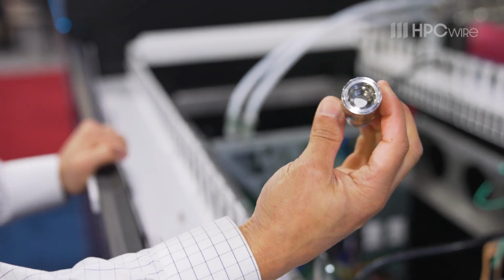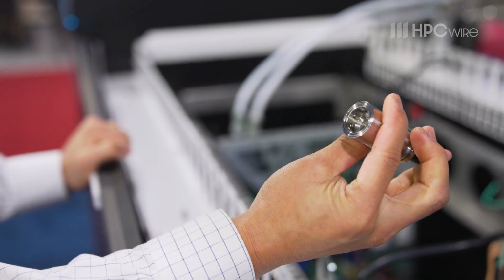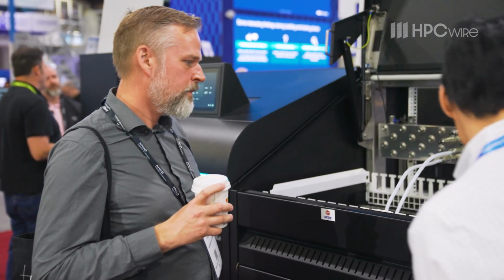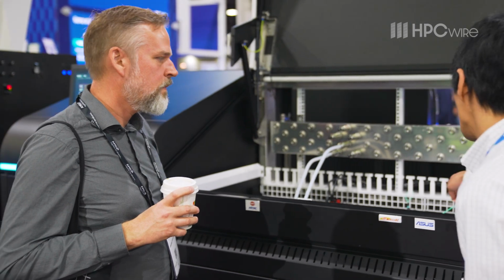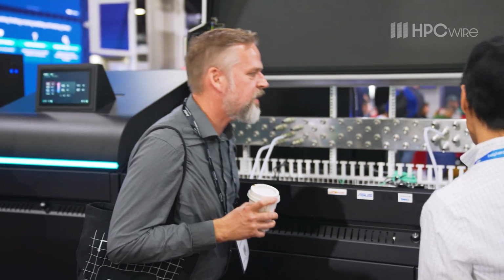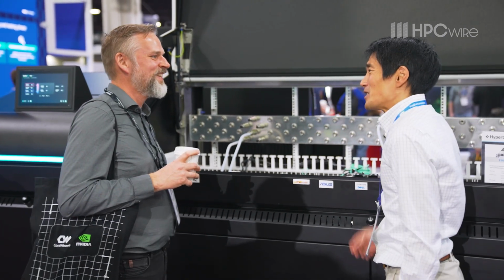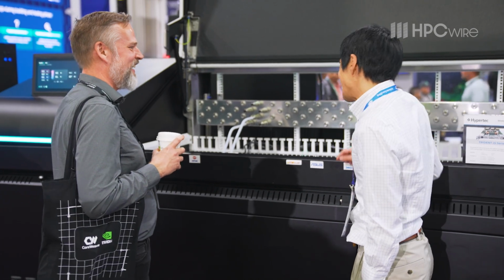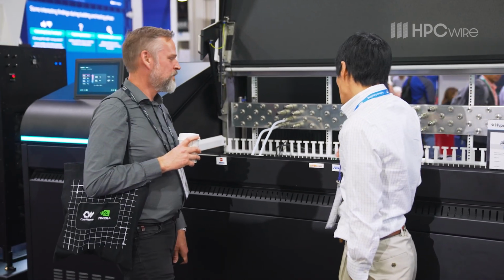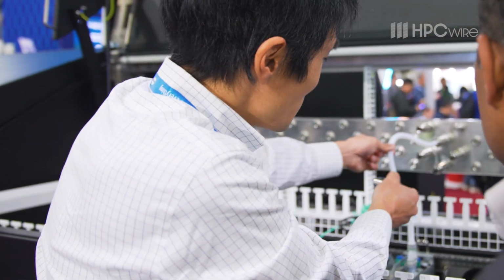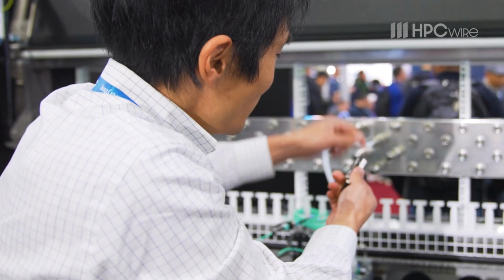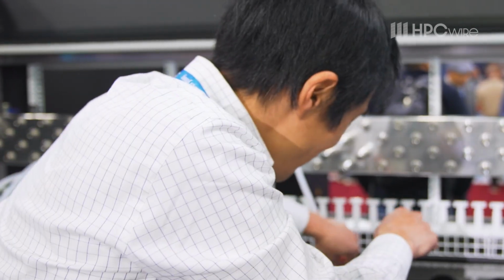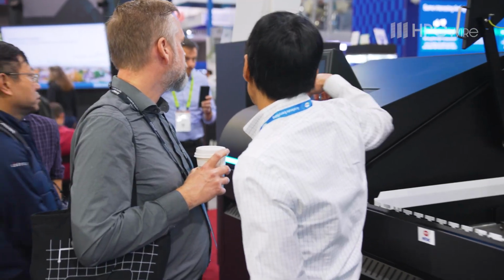Targeted flow technology works similar to DLC. You have a cold plate like heatsink on the CPU or the GPU. The main difference is that with DLC, the cold plate has an inlet and an outlet so the water can come from and to the manifolds. With targeted flow, there's only an inlet, so the fluid gets pumped from the manifold to the inlet, goes into the heatsink, through the microchannels, out, and up into the tank, back into the pump, and the cycle continues.